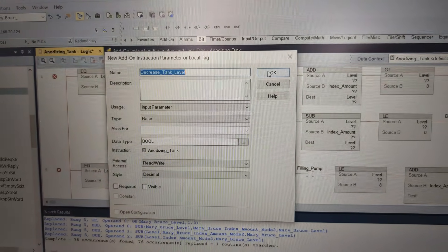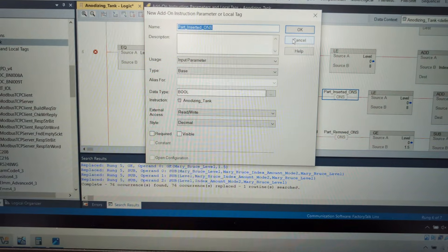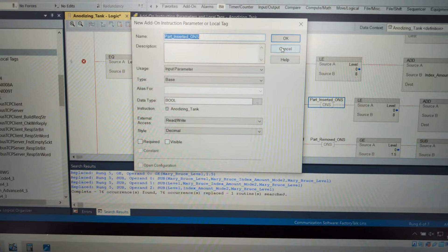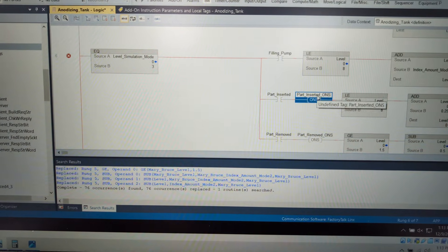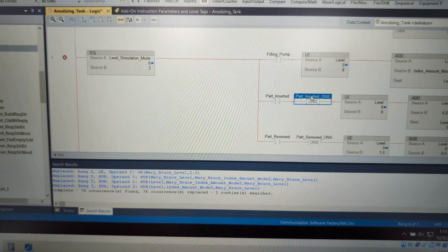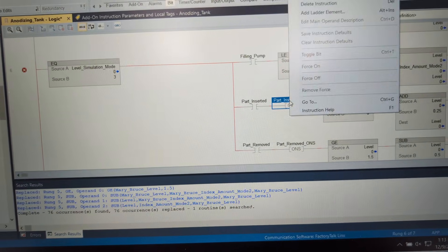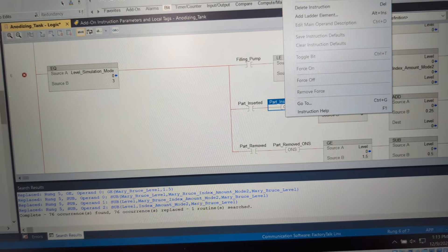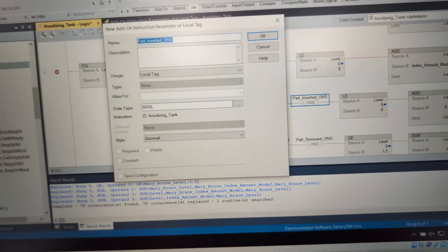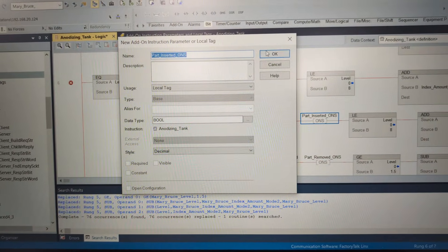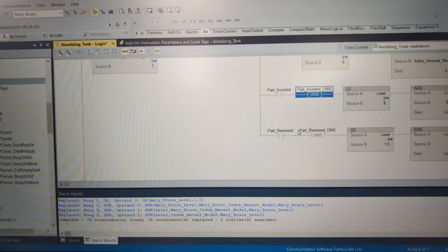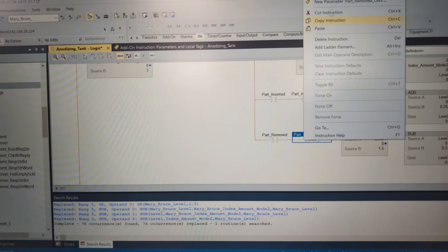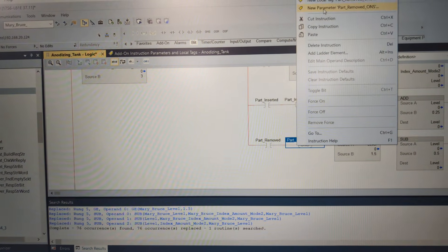You know what, I just stopped myself here. Here's a good example of a local tag. In here I do have a one-shot and we don't need to see that one-shot in our user-defined tags. This is a good example - we're going to right-click this one, we're going to make it a local tag. That way we're just not clogging up our user-defined tag that we're going to look at in a second with some of these items that you'll never need to look at.